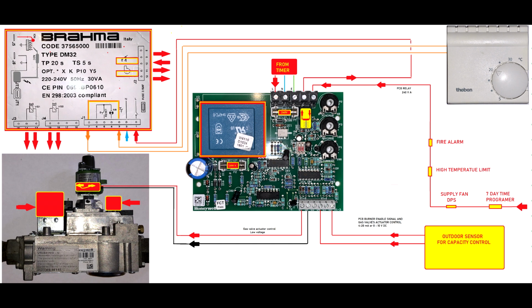Well, in this case you have to change the wiring a little bit, as you'll see here. Now the 4 to 20 milliamps or 0 to 10 volts will be connected straight to the bottom of this printed circuit board. Then you have a switch which will provide power to this printed circuit board, and the same switch will also provide power to this little relay on the printed circuit board. Then you have to install some safety devices in series. When you first start the timer, the signal will try to reach the printed circuit board and the relay which is on the circuit board.